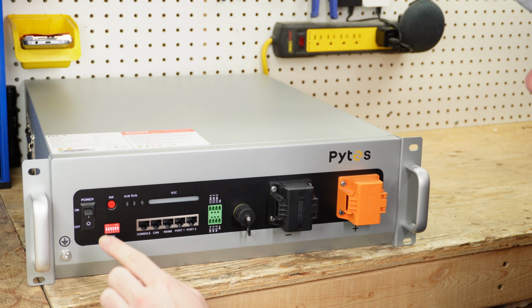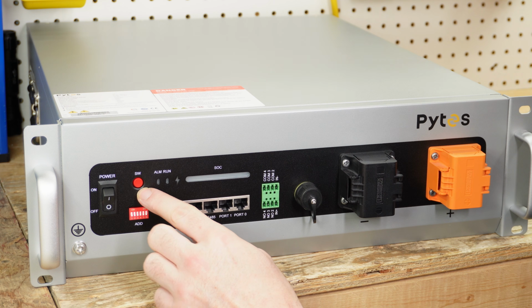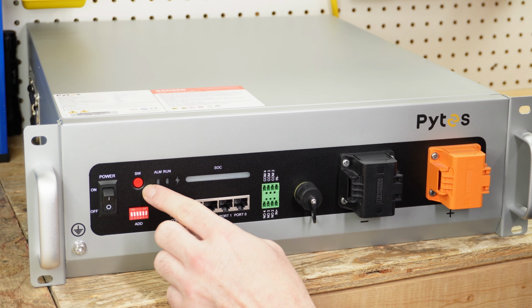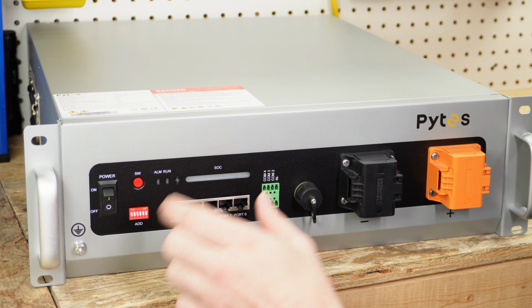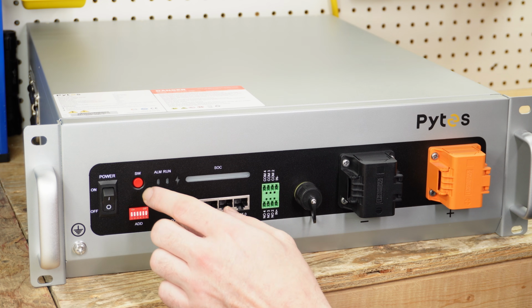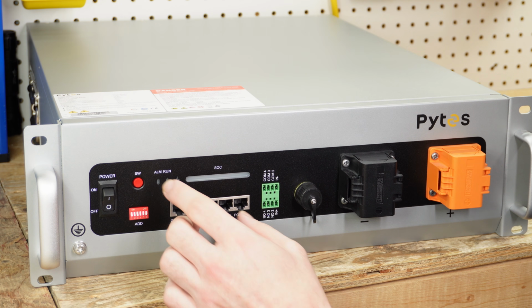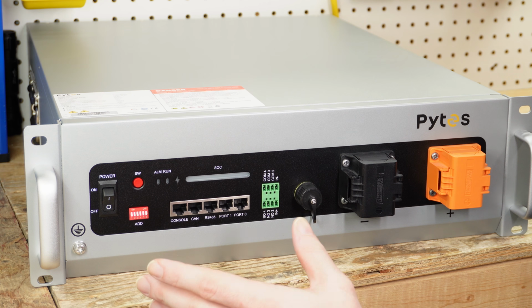Now looking at the front of the battery, we have an on-off switch and we have the startup switch. So this is going to be a soft start. So when you connect your batteries to your inverter, you're going to engage the soft start, and this is going to save your capacitors inside your inverter so that nothing breaks.